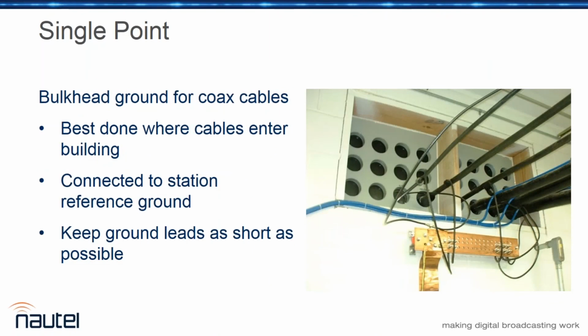The big thing with grounding, and you'll notice in this picture, we're showing a bulkhead ground for a bunch of coaxes leaving. There's a few things wrong. Number one, they're bolt-on connections, which with a bulkhead panel you don't have a lot of choice about. But number two, those straps are run around and looped, and they could be made quite a bit shorter if they ran down straight and came in from the top of the panel rather than going to the bottom like they are. So always think short, straight runs whenever possible for grounding. Have them connected to the station reference ground, and by all means use proper grounding kits.